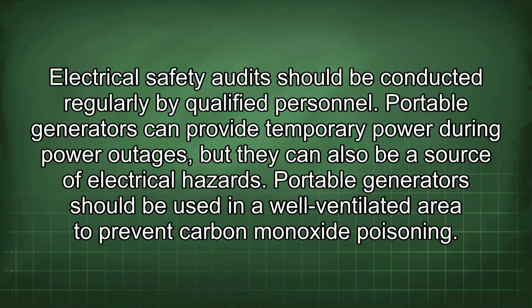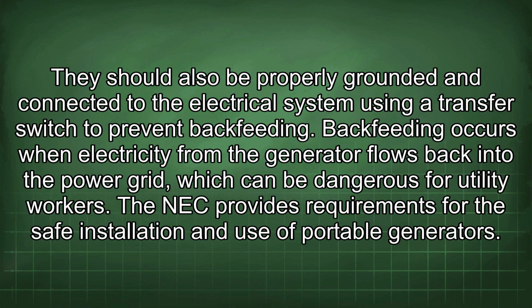Portable generators can provide temporary power during power outages, but they can also be a source of electrical hazards. Portable generators should be used in a well-ventilated area to prevent carbon monoxide poisoning. They should also be properly grounded and connected to the electrical system using a transfer switch to prevent backfeeding. Backfeeding occurs when electricity from the generator flows back into the power grid, which can be dangerous for utility workers. The NEC provides requirements for the safe installation and use of portable generators.